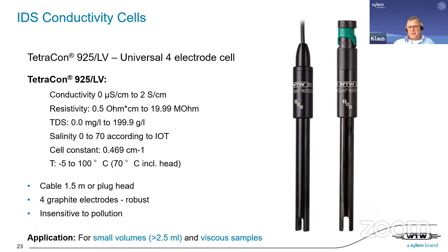And for the last people, who want to measure really in the pure water range, we also have a cell, which is the LR92501, a cell with a flow-through vessel. Of course, it's recommended to keep out carbon dioxide pollution. And this cell's measurement range is from 0.00 to 200 microsiemens per centimeter.